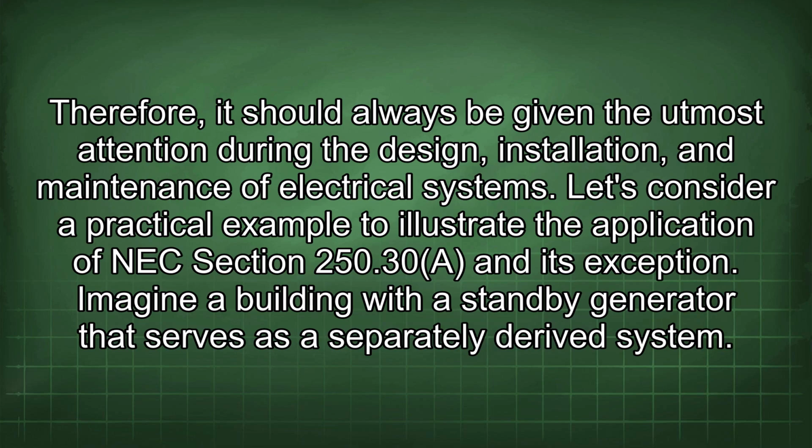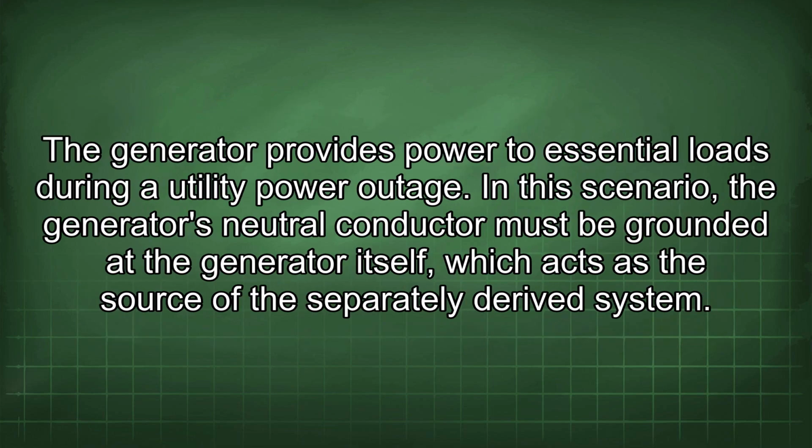Let's consider a practical example to illustrate the application of NEC Section 250.30 and its exception. Imagine a building with a standby generator that serves as a separately derived system. The generator provides power to essential loads during a utility power outage.